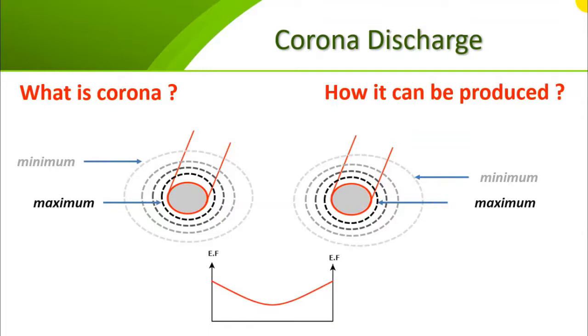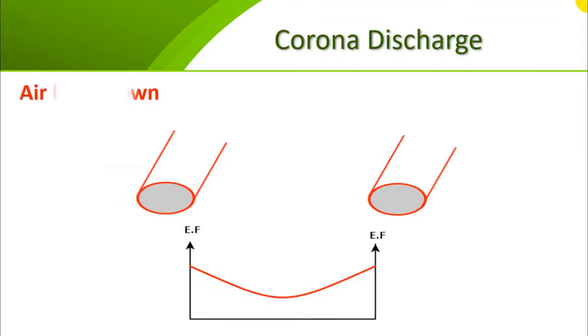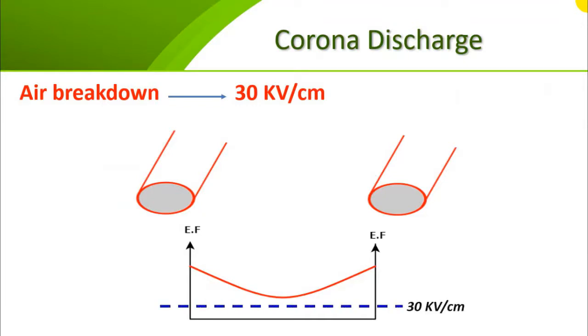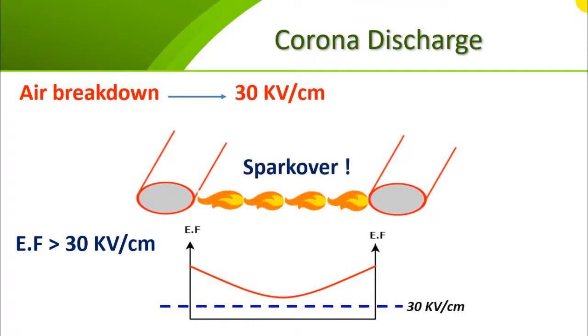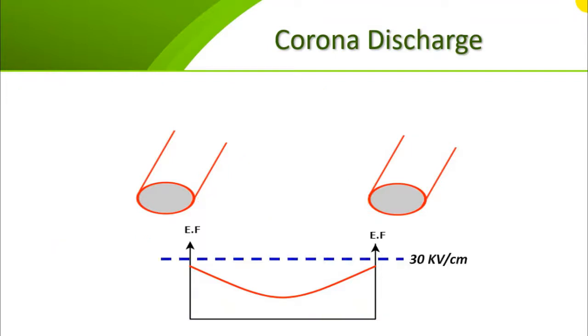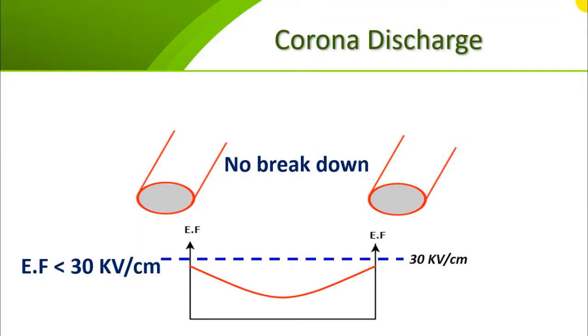Also, this graph shows the electric field near the conductor surface is maximum, and it decreases as we move away from the conductor surface until the electric field intensity becomes minimum at the midpoint between the two conductors. Also, you should know that the air breaks down when subject to an electric field equal to 30 kilovolt per centimeter or more. Therefore, if the electric field produced by the conductors exceeds 30 kilovolt per centimeter, the air breaks down and spark over takes place in the air between the two conductors. Also, if the electric field produced by the conductor is less than 30 kilovolt per centimeter, no breakdown will occur and there is no problem with that.